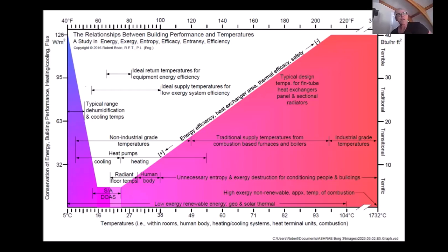And when we do that, what you find is that as the loads go down, the compliance goes up. And then what you can do with this information, with electrification and decarbonization, is you can take heat pumps and marry them up to large surface area heat exchangers, which drops the temperature down in heating and increases the temperature in cooling, which then increases the efficiency of the chillers and the heat pumps and the boilers or solar systems or whatever it is that you're using. And by doing that, you're actually getting what's called high exergy efficiency. In other words, there's low entropy. So anytime you can marry renewable systems to heat pumps to large surface area heat exchangers, it will never get any better than that in our lifetime in terms of exergy efficiency.